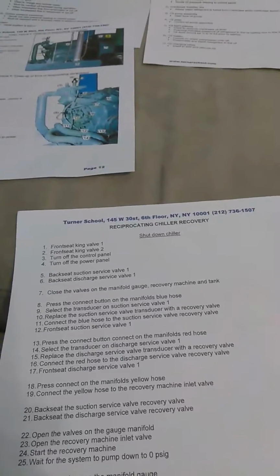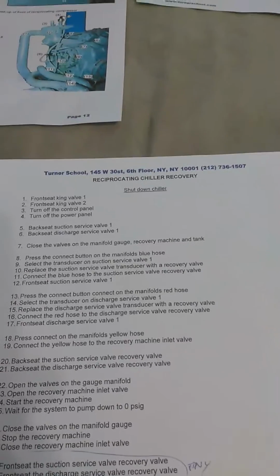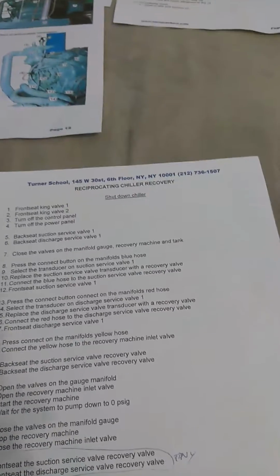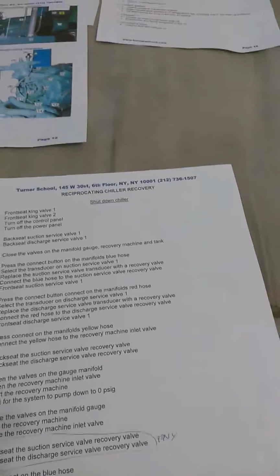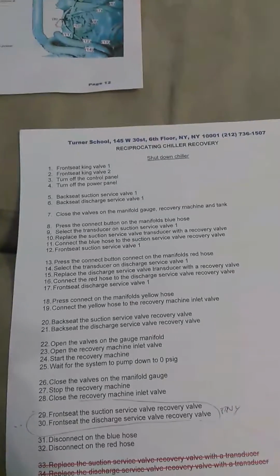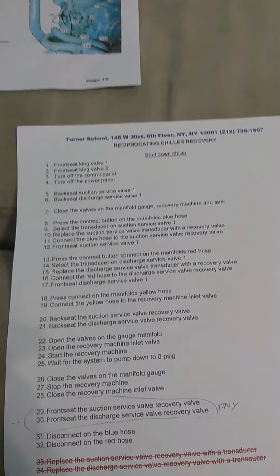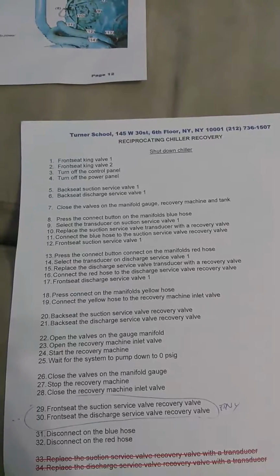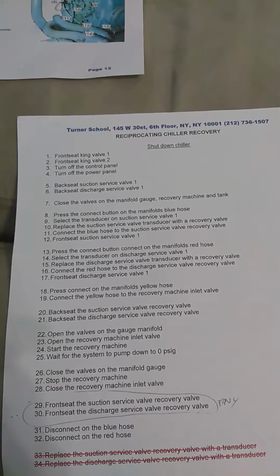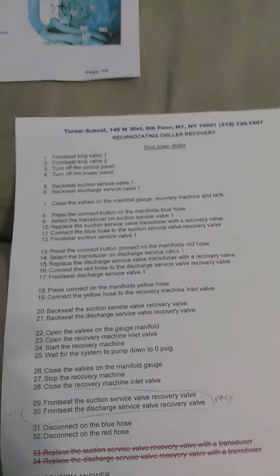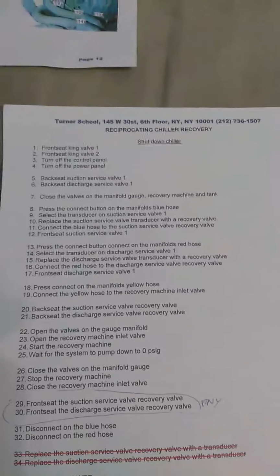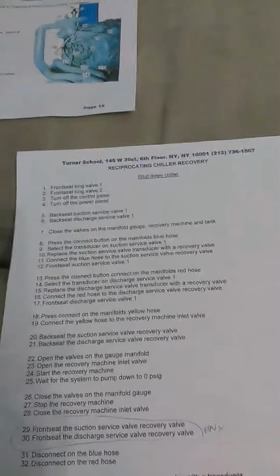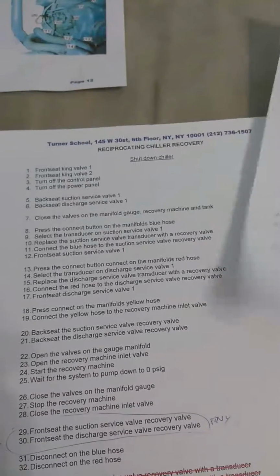Okay, we're going to do recovery again. Front seat the king valve. Turn off the control panel. Back seat suction service valve. Back seat discharge service valve. Close the valves on the manifold.